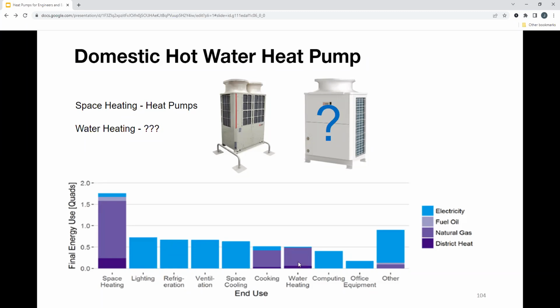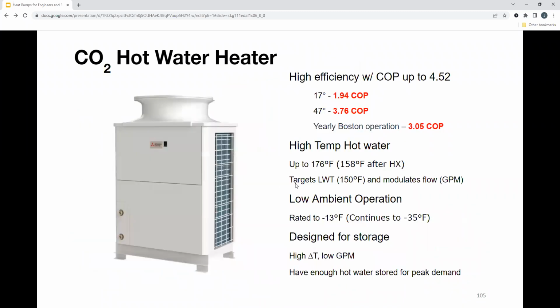So, are there solutions out there on a centralized scale for domestic hot water? And the answer is yes. There is a CO2 hot water heat pump. CO2 is actually the baseline of GWP. It equals 1, so no global warming potential there. And what it is, is a heat pump that has CO2 installed right inside here, and then you have water piping going out to a heat exchanger, and then feeding storage tanks.